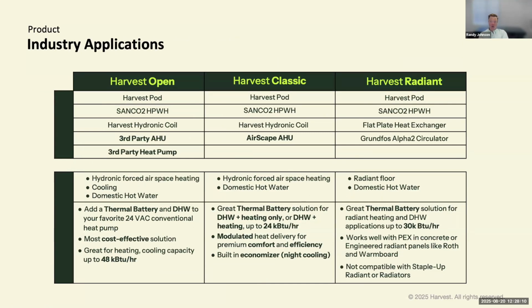We do have a growing number of radiant projects as well. And Brett is in the process right now of deploying our first radiator replacement retrofit in the Bay Area as well, in an Eichler. So, if we want to get into the technical details, typical boiler systems with radiators are designed to operate at between 170 and 180 degrees Fahrenheit.